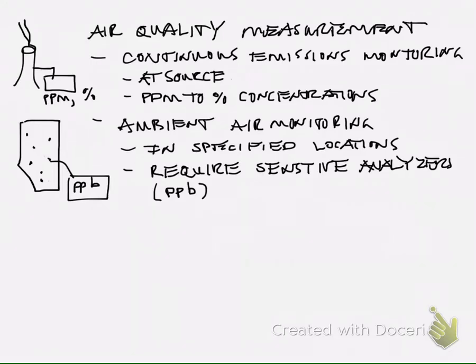Strategically placed throughout the province, and they require sensitive analyzers down to the parts per billion range, because we're dealing with concentrations that are a lot lower. We're not right at the source now. So we need analyzers with high sensitivity for ambient air monitoring.